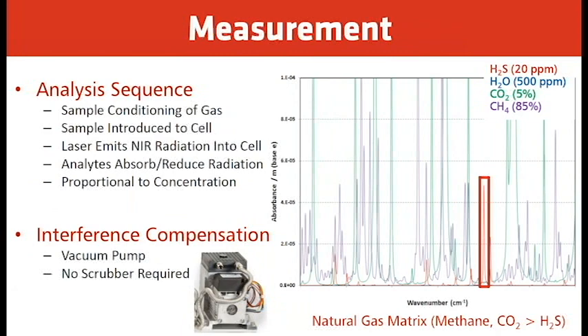Now, on the right side, you see that graph. This basically shows you the absorption spectra for different species, including H2S, in the background of other gases, obviously, for example CO2, moisture, and depending on the stream, other things. So although interfering species might exist in the stream, the way our laser works is that we use the vacuum pump in our system. The whole idea is to keep a partial vacuum pressure in the cell, so we are able to isolate the line that is of our interest, in this case this red one here, for the measurement, without worrying about what else is going on in terms of the other species. So we isolate that line, and there is no interference from any other component.